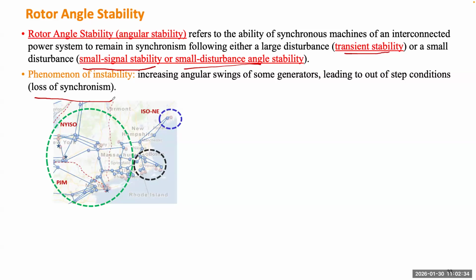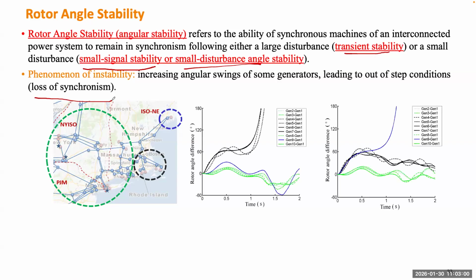One example is this model of the Northeastern power system. It has 3 groups of generators. Each group tends to become coherent following any disturbance, which means the generators inside each circle try to stay together. But if you have some disturbance, the 3 groups of generators may oscillate against each other. There are 2 scenarios. The first is this black group, which speeds up and diverges from the rest of the system. And the second scenario is this blue group, which is basically one power plant in Canada, flying away from the rest of the system. Both scenarios are considered rotor angle instabilities.